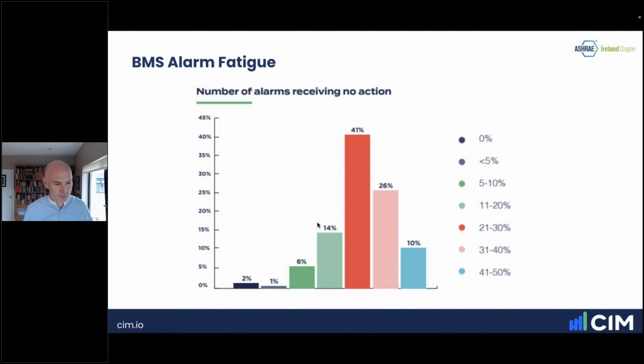Reflecting on some of the sites I worked in throughout my career, when facility technicians weren't sitting in front of the BMS watching which alarms were being flagged and whether they should be actioned, outside of working hours that job typically went to a security guard. In most sites, the BMS would trigger a critical alarm, say a chiller stopped or something like that, but for all other types of alarms, the security staff had the ability to silence or dismiss them. That really resonated with me, the fact that a lot of alarms are flagged but there's no action executed on the back of them.